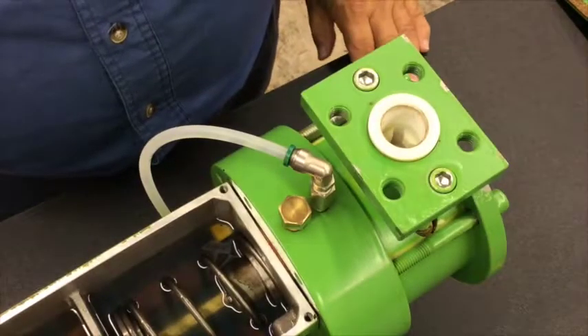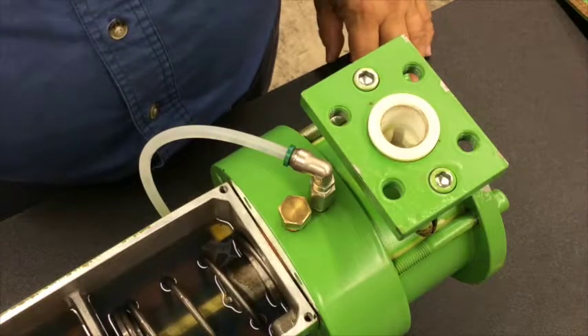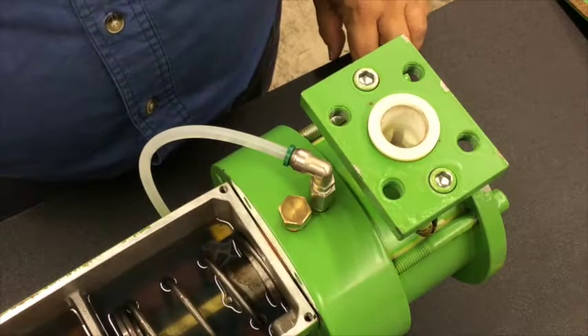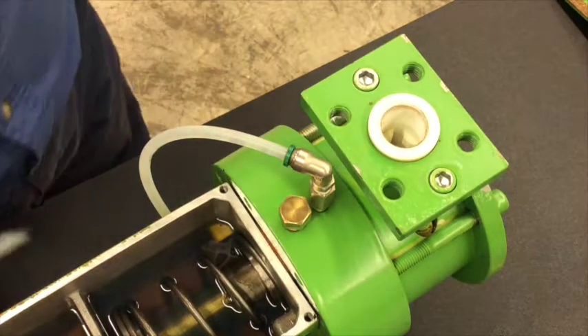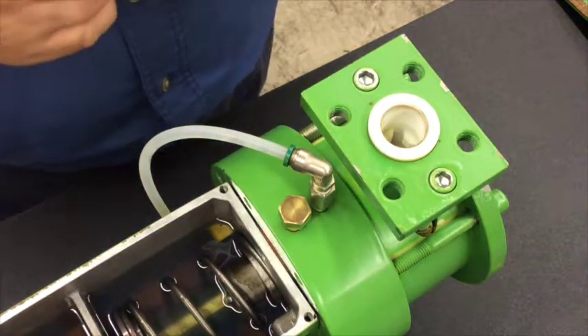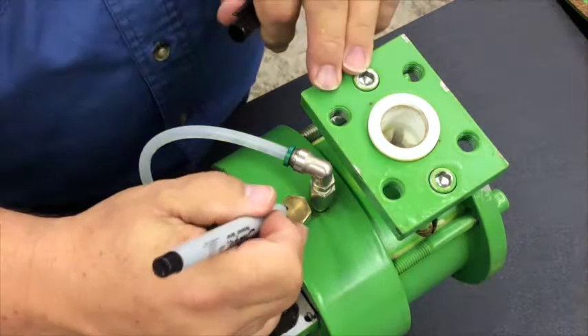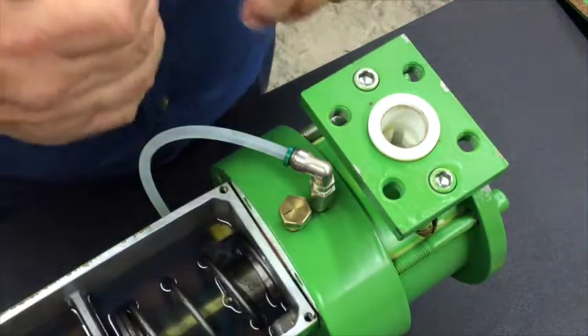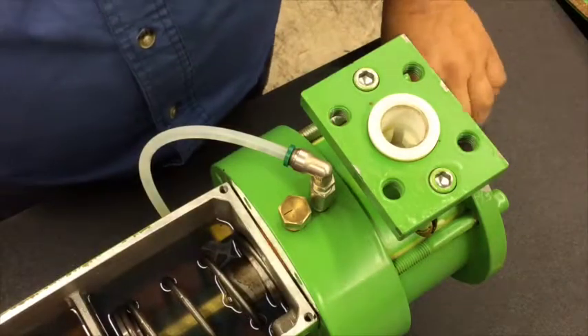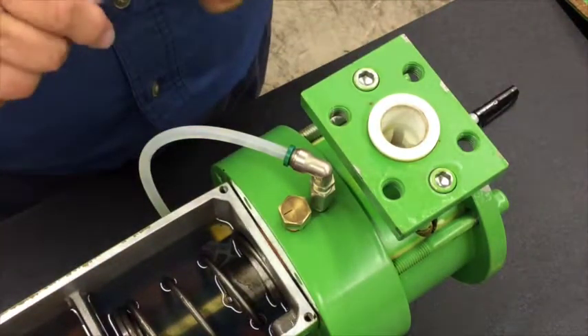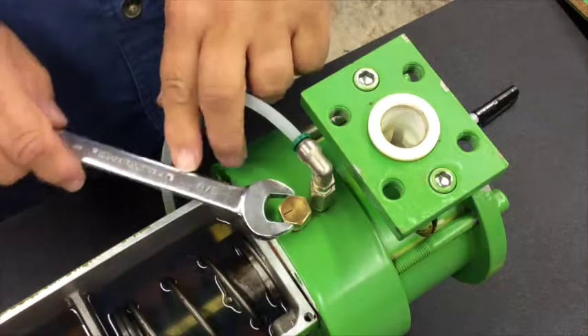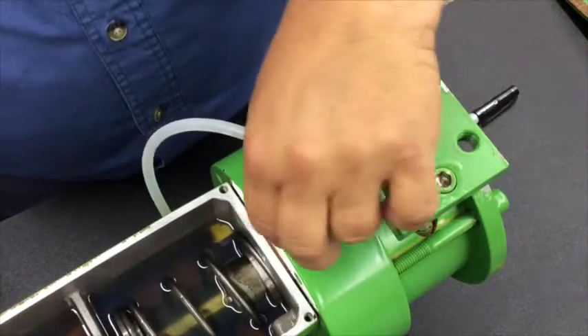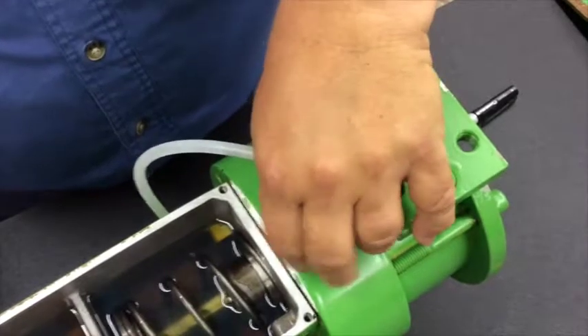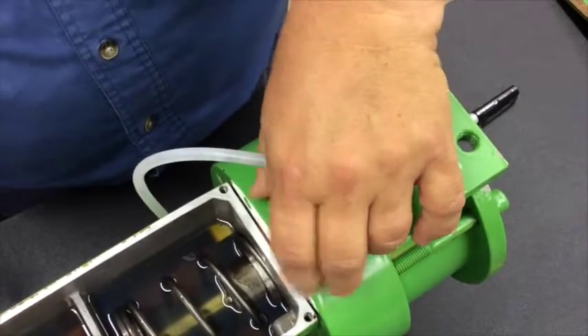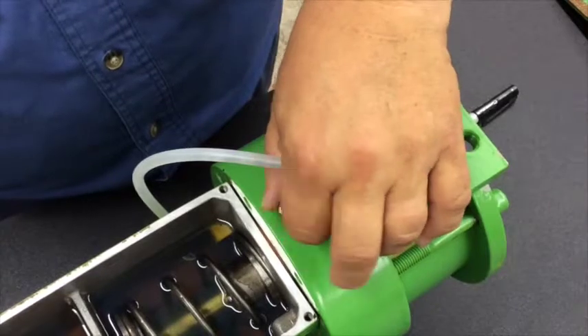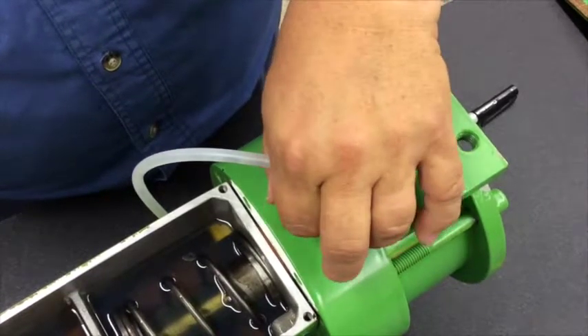Right. My next step is that I'm going to remove the hydraulic bypass adjustment screw. And I want to make sure that I return this adjustment back to its original position. So what I'm going to do is put a mark on it, and then as I unscrew it, I'm going to count the revolutions. Okay. This is where I'm going to use that 5/8 inch combination wrench. So 1, 2, 3, 4, 5, 6, and I'm out.